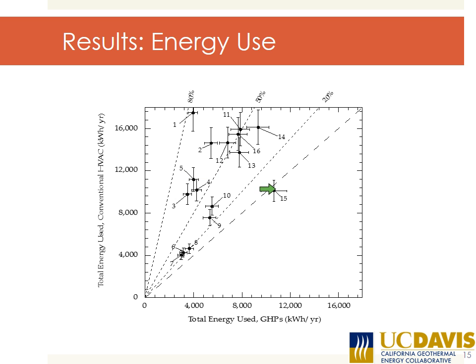Climate Zone 15, in the Imperial Valley, is predominantly a cooling environment, and in that situation the heat pump in cooling mode was not as efficient as the standard HVAC system at the time we modeled this, several years ago. Geothermal heat pump systems have since increased in efficiency tremendously. If we redid this study now, all points would fall above and to the left of the dashed line, including the Imperial Valley—meaning energy savings would be achieved in any California climate zone using modern technology.